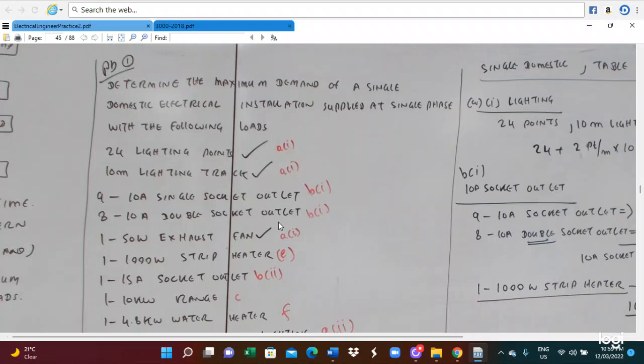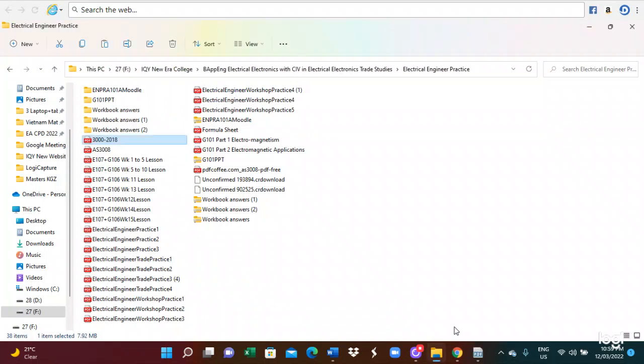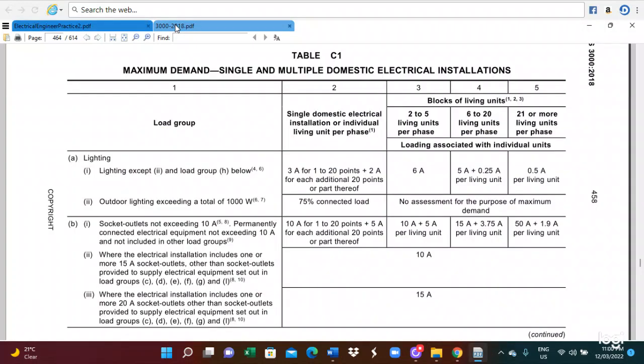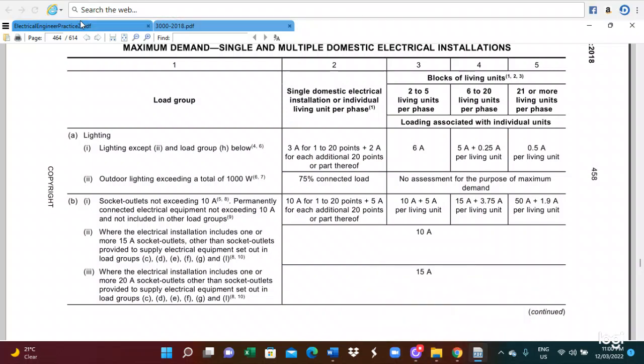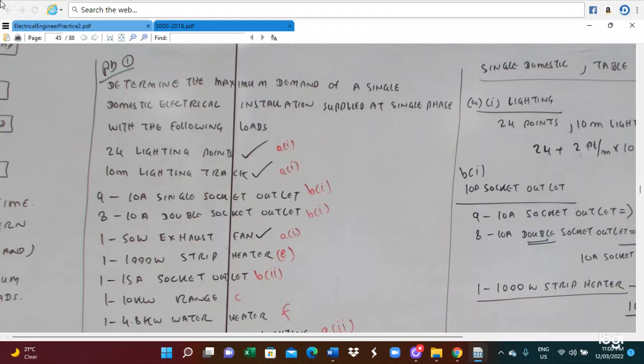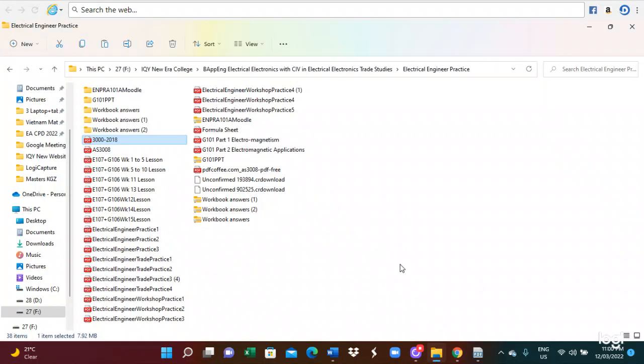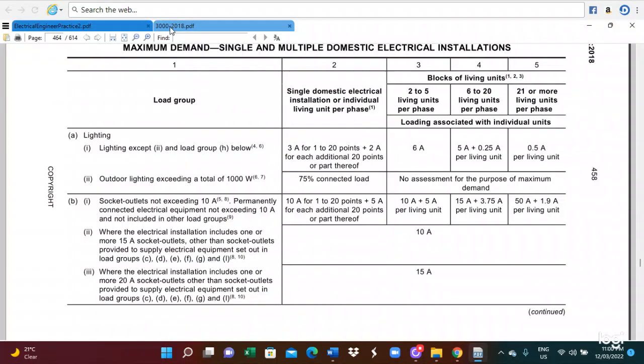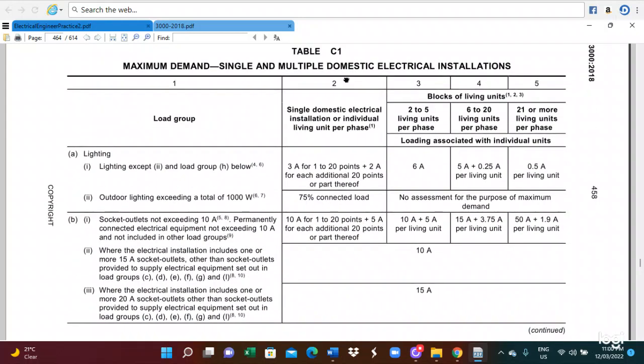Based on those electrical loads, we need to calculate the maximum demand, and for the calculation we have to utilize AS3000. This is AS3000 table C1, located at page 464. Firstly, we have to see which loads are utilized. This is for the consumer installation, and this consumer installation is a single domestic electrical installation. Here, column 2 is single domestic electrical installation. Columns 3, 4, 5 are for blocks of units: 2 to 5, 6 to 20, and 21 or more. In this case the problem gives a single domestic electrical installation, therefore we have to refer to column 2.